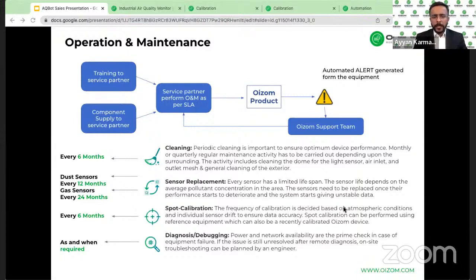The spot calibration may be done every 6 months. Even that depends on the environment that it is in, and we can definitely discuss with our support team and they'll guide you better. There are certain consumable parts like the dust sensors and the gas sensors, which need to be replaced at regular intervals depending on the environmental conditions. However, our remote support team is always available for troubleshooting. The system will also generate alerts, which will be sent to our team, who can then guide the local technicians to make any required changes. So this is all about the support and operational maintenance of the AQBot product.